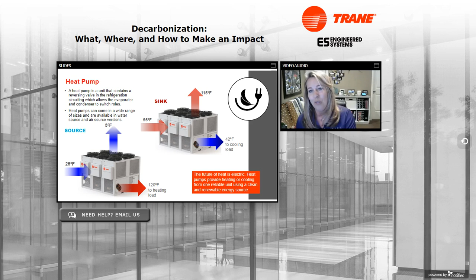When a heat pump is in cooling mode, it operates just like a chiller. It's producing cold water from a cooling load, and it's rejecting heat into that sink. When the heat pump is in heating mode, that reversing valve has changed directions. So our evaporator and condenser, or our source and sink, have switched roles. And we are now providing heat, pulling that from the source, satisfying the load in the building. Heat pumps are great for any building that has a heating load in the winter and a cooling load in the summer.